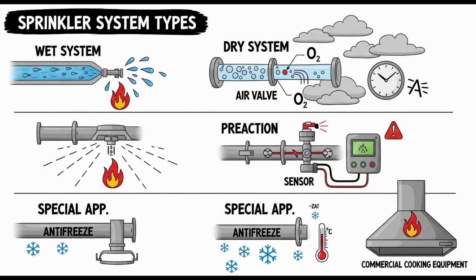That's incredibly precise. Yes, it shows the concern that even small projections can effectively shield the area below them, like the window opening itself or the wall surface, from the water spray coming from sprinklers located higher up. You need direct application. Okay. For general wall protection, where are sprinklers placed? Typically located 6 to 12 inches horizontally away from the wall surface and vertically within 6 inches of the top of the wall section being protected. Maximum spacing along the wall is usually 8 feet, or as per the sprinkler's listing. This placement ensures the water effectively wets and cools the wall surface as it flows down.